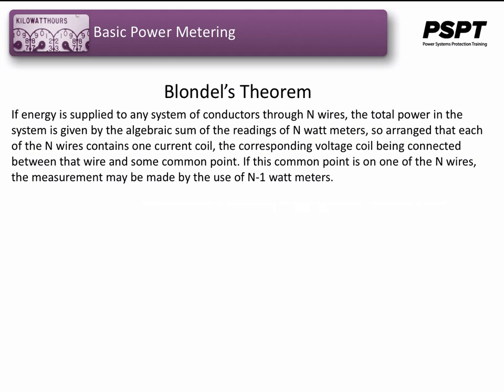Blondel's theorem states that if energy is supplied to any system of conductors through n wires, the total power in the system is given by the algebraic sum of the readings of n wattmeters, so arranged that each of the n wires contains one current coil, the corresponding voltage coil being connected between that wire and some common point. If this common point is on one of the n wires, the measurement may be made by the use of n-1 wattmeters.